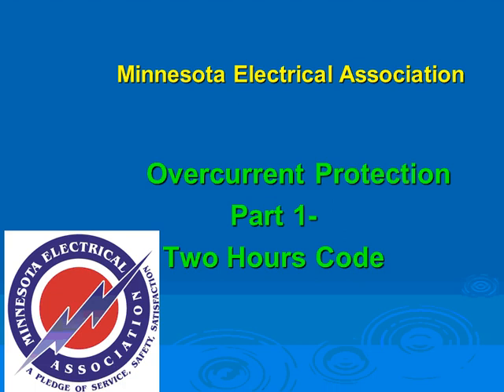Okay, overcurrent protection device. So we picked a couple of things for you about overcurrent protection devices. I don't know how many of you have dealt with higher than 600 volt. If you do, you know that overcurrent protection is only one function that will protect the power system. There's over/under frequency, over/under voltage, directional current, and open phasing on certain equipment. So there are many aspects that a power system needs to be protected from. The notoriously famous, easiest way of protection is from overcurrent.